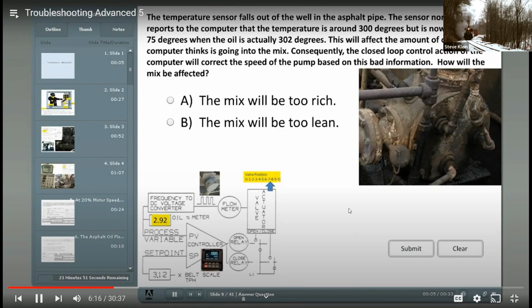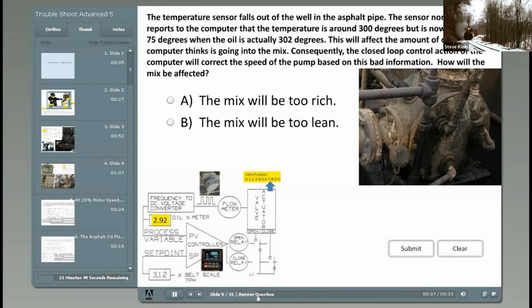Sensor falls out of the well in the asphalt pipe. The sensor normally reports to the computer that the temperature is around 300 degrees, but it is now reporting 75 degrees when the oil is actually 302 degrees. This will affect the amount of oil the computer thinks is going into the mix. Consequently, the closed-loop control action of the computer will correct the speed of the pump based on this bad information.